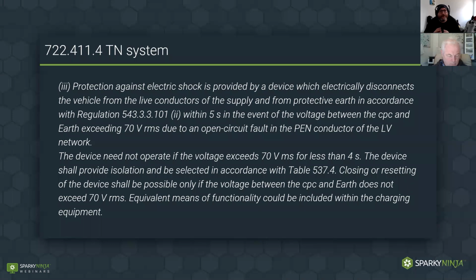Now, we had this third one, and there's not much change to it except for the guidance. Unfortunately, it's lots of words, and I have to read it, I'm afraid. Here we have a device, and it's going to electrically disconnect the vehicle from the live conductors of the supply and from the protective earth in accordance with 543.3.3.101(ii), which actually means if you go to devices that switch the protective conductor, this device has to switch the protective conductor after the live, and make it before. A bit like how we would switch neutrals, we must make sure the protective conductor is not disconnected first and reconnected last. That's just the switching requirements of a protective conductor. That's what goes into that regulation there.